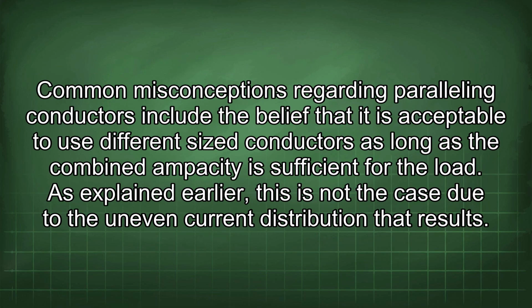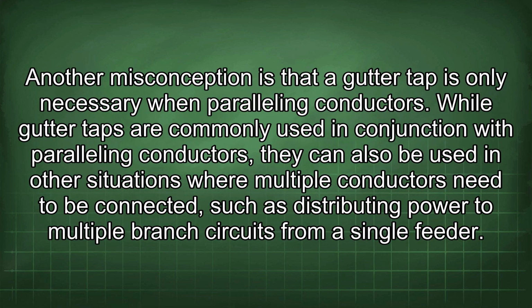Common misconceptions regarding parallel conductors include the belief that it is acceptable to use different sized conductors as long as the combined ampacity is sufficient for the load. As explained earlier, this is not the case due to the uneven current distribution that results. Another misconception is that a gutter tap is only necessary when paralleling conductors. While gutter taps are commonly used in conjunction with paralleling conductors, they can also be used in other situations where multiple conductors need to be connected, such as distributing power to multiple branch circuits from a single feeder.